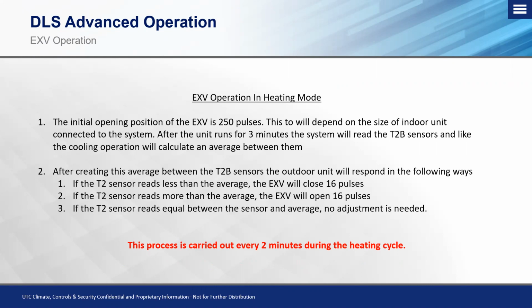After that unit runs for 3 minutes, just like we did in the cooling mode, the system will read the T2B sensors, and like the cooling operation, will calculate an average between them to figure out what the average temperature is. If we go above it and below it, we need to either open or close the valve appropriately. So after creating this average between the T2B sensors after 3 minutes of runtime in the heat mode, the outdoor unit's EXVs will respond in the following ways. If the T2 sensor reads less than the average, the EXV will close 16 pulses. If the T2 sensor, and this one actually should be T2B, excuse the typo on the slide. If the T2B sensor reads more than the average, the EXV will open 16 pulses. And finally, if that T2B sensor reads equal between the sensor and the average, we don't have to adjust it.